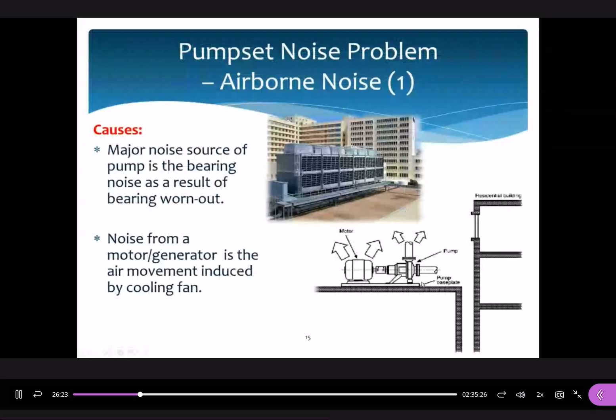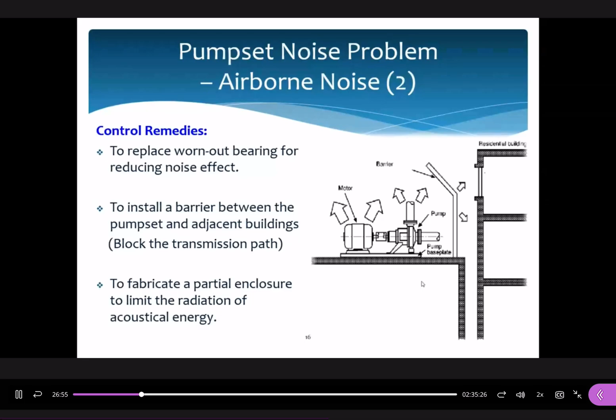The control remedies in terms of airborne noise: we may do regular maintenance for those mechanical components. The second one is to install a barrier, a partial barrier between the pump sets and the adjacent buildings, in order to reduce the noise effects. The third one is similarly a kind of partial enclosure to limit the radiation of acoustical energy. For the second and third points, the working principle is the same: to install an obstacle between the source and the receiver.